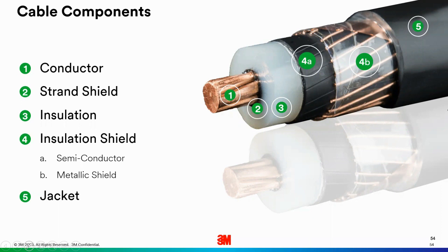Moving on down, the next one would be the strand shield, number 2 there. And that's basically a semiconductive layer located between the insulation and the conductor, and it acts as kind of like keeping out air voids between the insulation and the conductor. Your insulation is next, and you'll see different colors of insulation. So you'll see like white or clear. You might see like a pinkish or orangish color. So this would be like EPR rubber, ethylene propylene rubber, commonly referred to as EPR, versus XLPE, which is the cross-linked polyethylene. And then in some cases, I'm seeing it a lot out there in your area, is the PILC, the paper insulated lead covered cable that is still in the ground today.